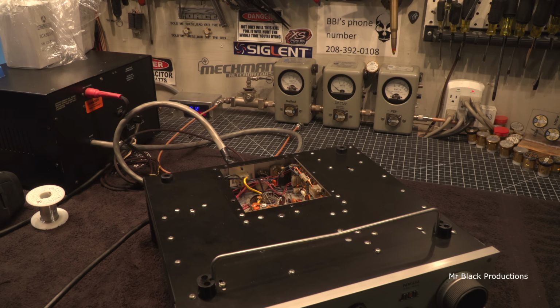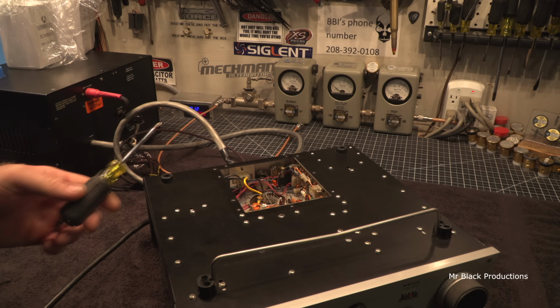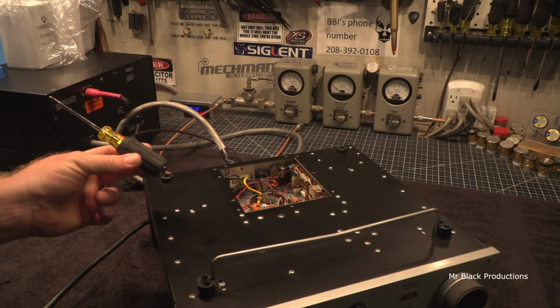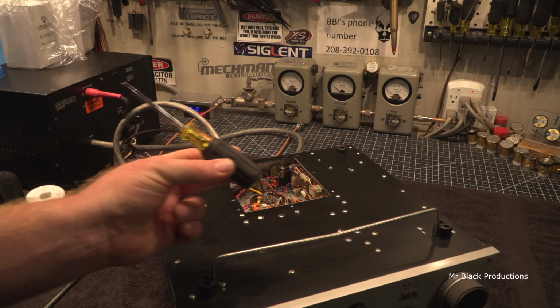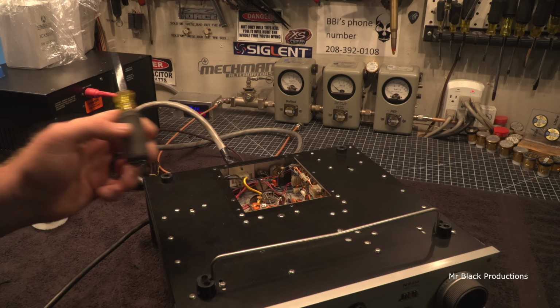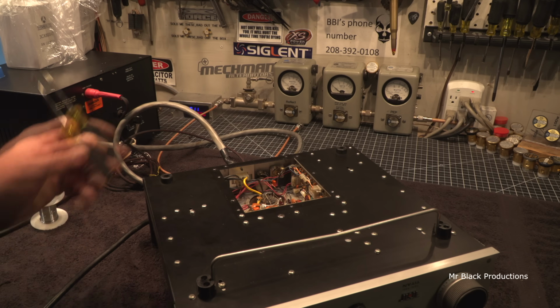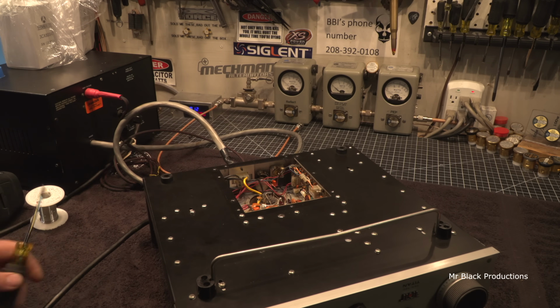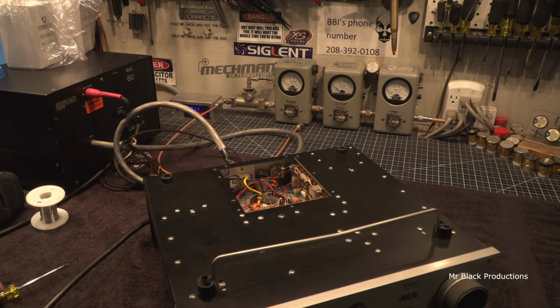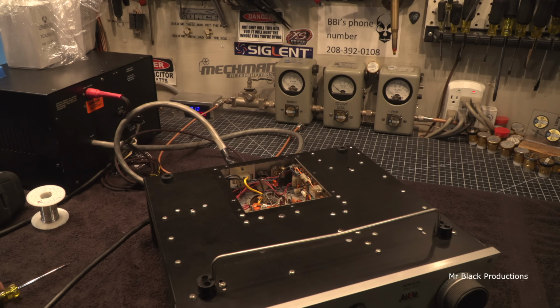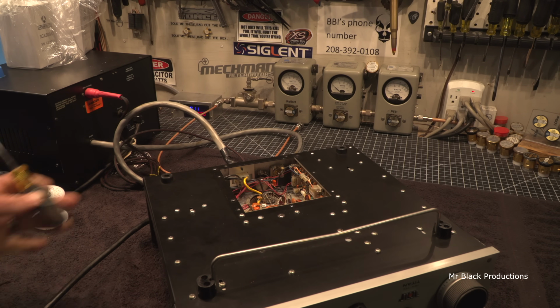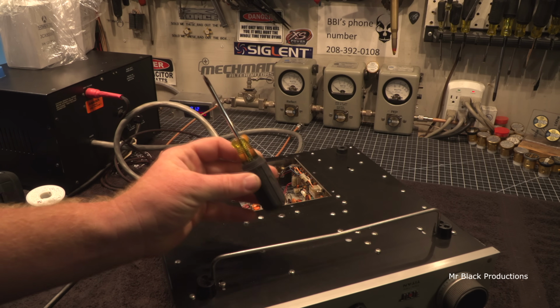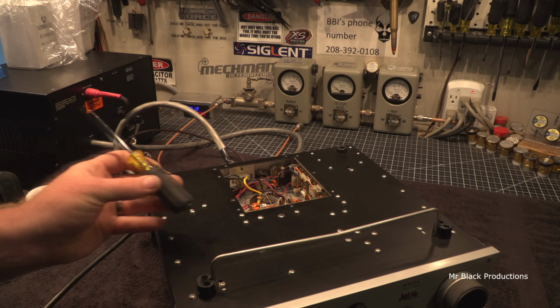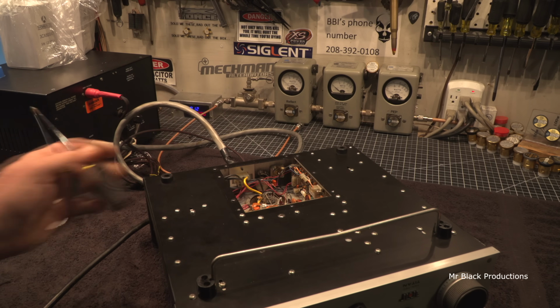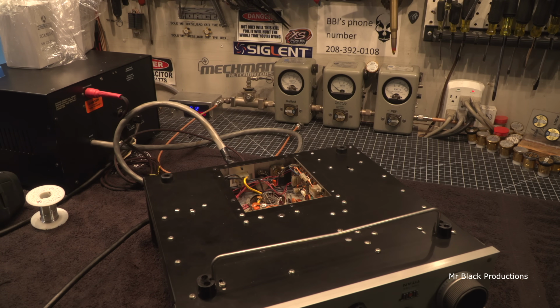It's something timed, because you can hear the power supply. It'll sit there and run, and then all of a sudden it goes dong, just like instantly, like somebody flipping a switch. Then it'll run and I get transmit mode. It'll come out as standby, which is just the timer counting down, and it's very consistent - about 20 to 30 seconds into it being on, then it'll go click. Something inside here goes click. So I've got to measure what's changing in the deck.